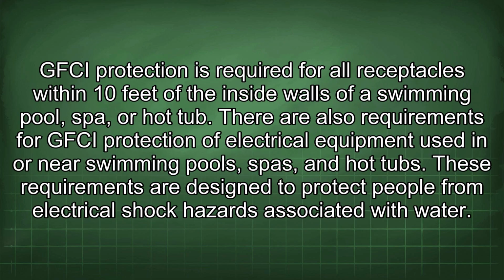GFCI protection is required for all receptacles within 10 feet of the inside walls of a swimming pool, spa, or hot tub. There are also requirements for GFCI protection of electrical equipment used in or near swimming pools, spas, and hot tubs. These requirements are designed to protect people from electrical shock hazards associated with water.